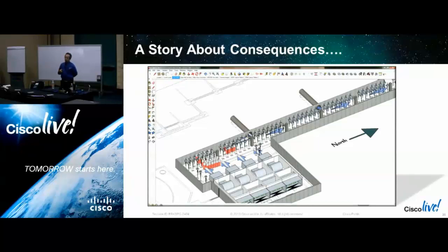They knew they had a contamination problem. We found that they had actually 4 vectors of contamination that were sodium-based, and in fact had done a deep cleaning of the data hall, including the underfloor spaces and the racks, about a month and a half prior to the failure event, which obviously had increased the amount of contamination that was airborne and brought into the IT gear.